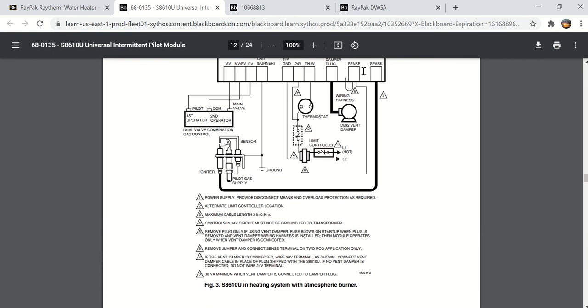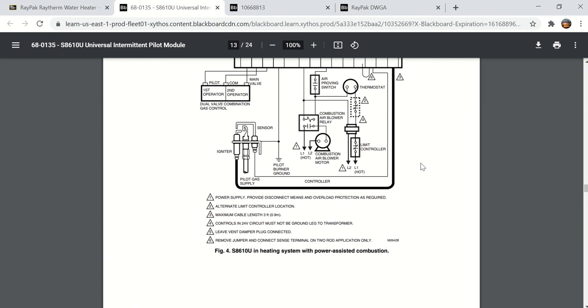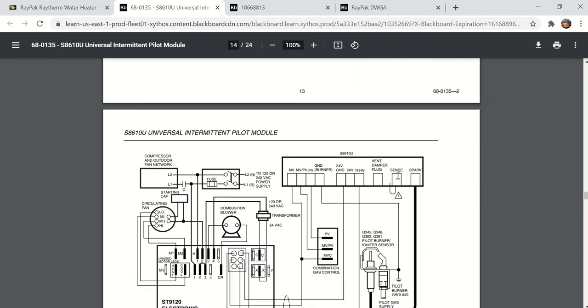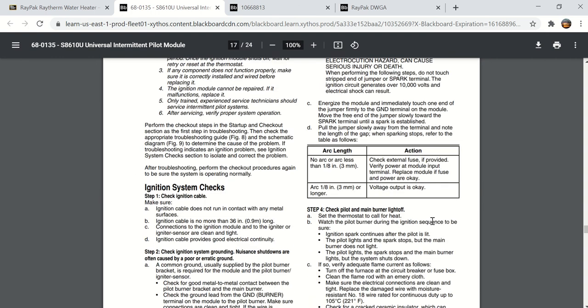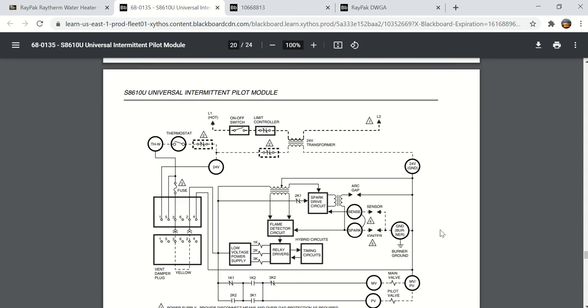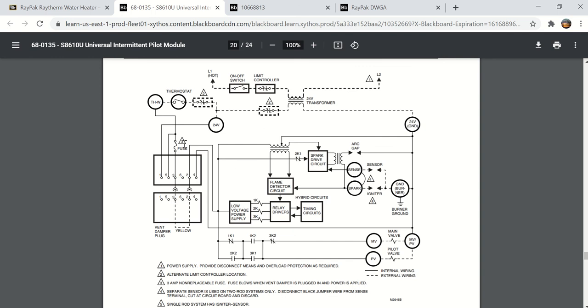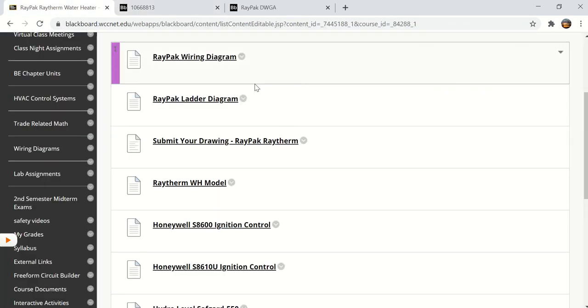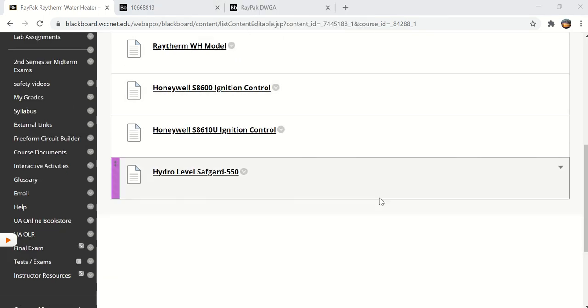Some more drawings. Here's where they use spark and sense, and then there's other ones that are just single. Like right here, you don't have the sense, you just have the spark. And at the end of this manual for the Honeywell S8610U, it gives you a little bit of information, like you saw with the flame safeguards, where the internal circuitry is and how it controls the main valve and pilot gas valves. Okay, last thing to go over, and then I'll make up maybe 10 questions. Each will be worth 5 points, and that'll be 50% of your grade, or 50 points of your grade, from the quiz. The other 50 points will come from the drawing that you do by hand.